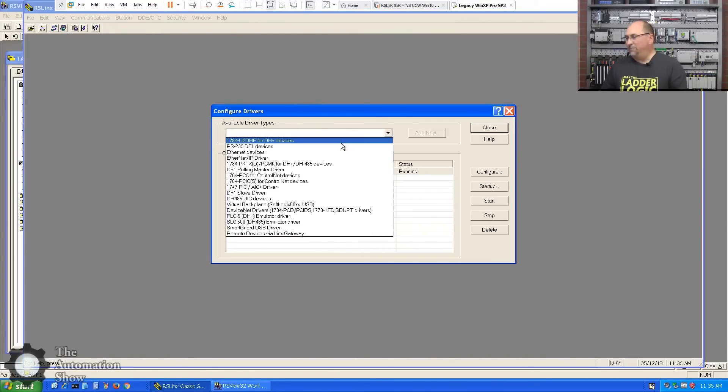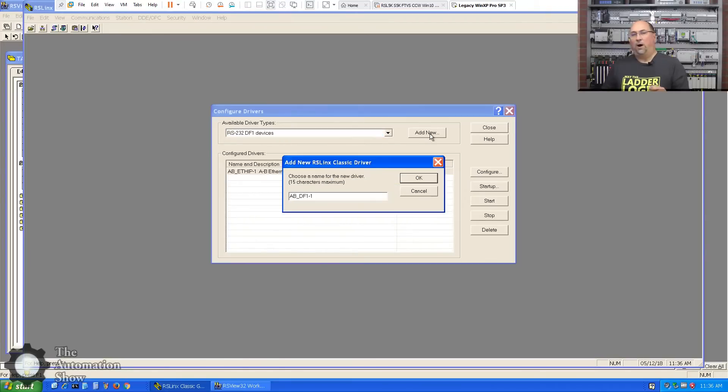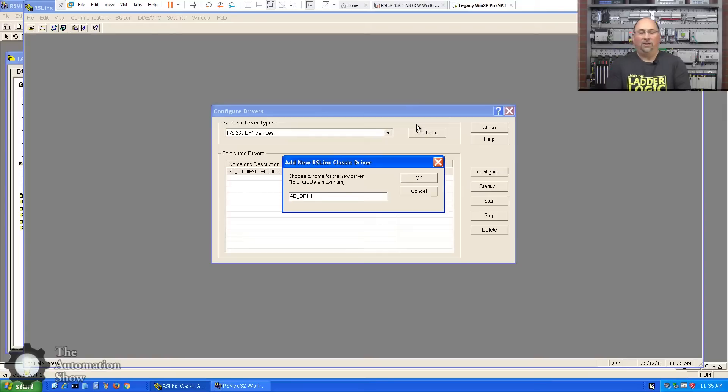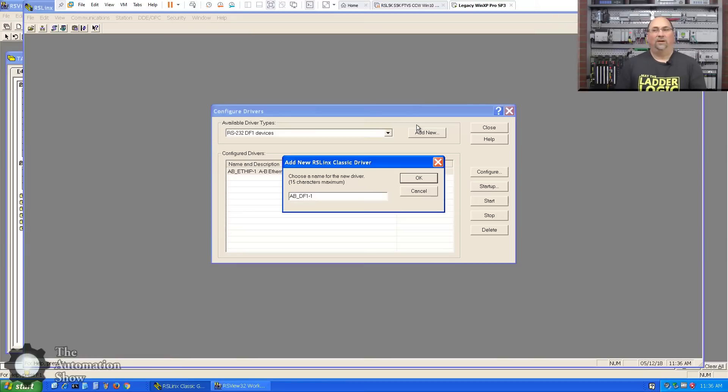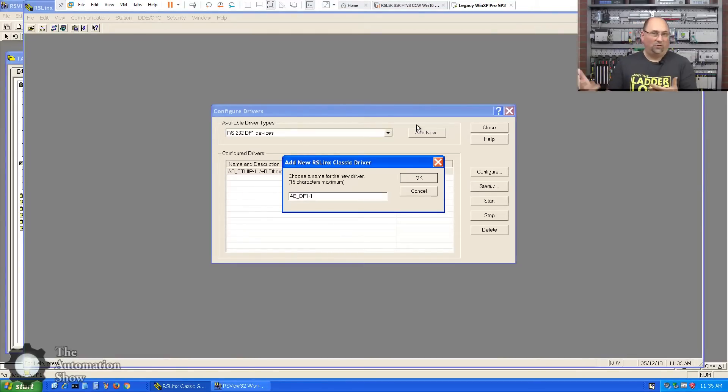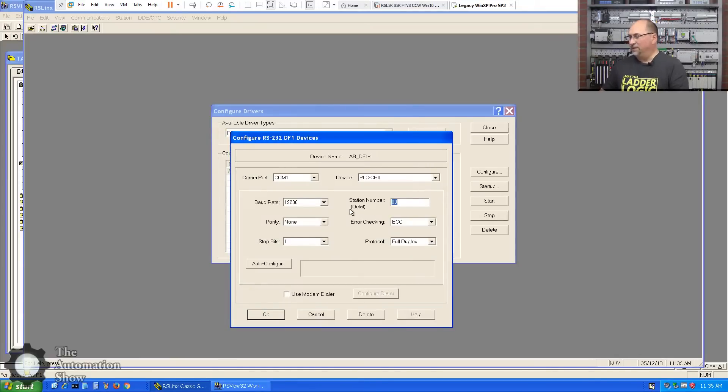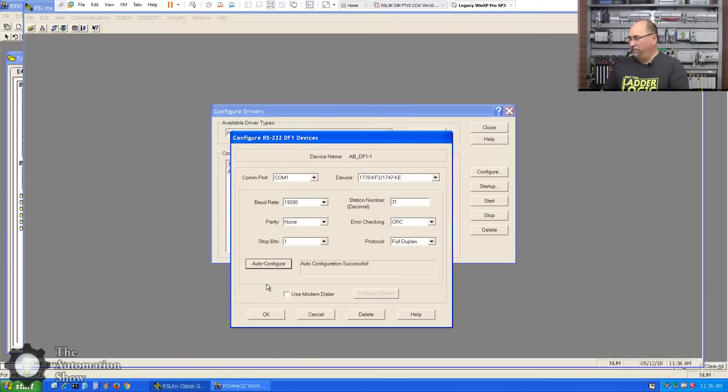The first one I'm going to add is an RS232 DF1 Devices driver for our KF3. If you've watched the previous episodes, you know we've been using a KF3. I am on the hunt for a PKTX card. Right now they're all kind of really pricey, around $200, so trying to find one in the used market that's very inexpensive. So we can maybe try setting that up and see how that works. But in any case, this will be our KF3 that's on COM1 now, and I'm going to switch it over to KF3 and I'll do an auto config. And it's successful, excellent.